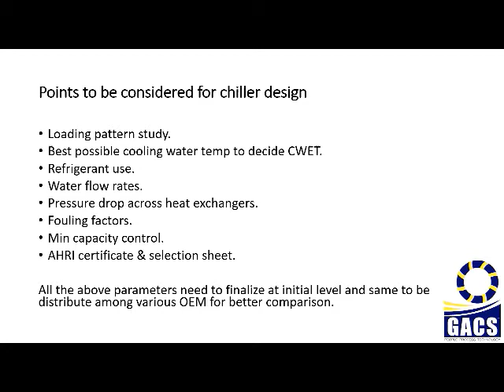So now coming to the weather data or the operating envelope of a particular location. Now the point comes regarding the VFD on the chiller, right? So we can study the loading pattern as well for choosing the role of VFD. We can study the weather pattern or the operating envelope of that site, of the building, before selecting the VFD based chiller. So you can see here in this graph, left side graph, it can be seen that 99% of the total time, means out of annual running hours, 99% of the time the machine runs on part loads, right? So only 1% of the time the machine runs on full load design conditions, which we select.